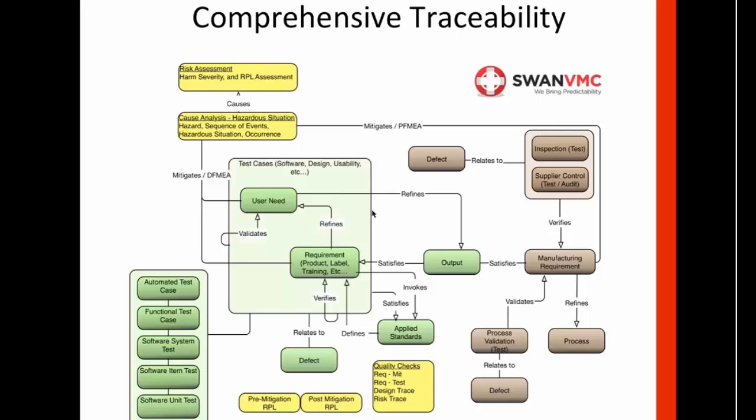So that's kind of the manufacturing piece of the flow chart. And of course, now when you overlay the yellow part, which is the risk management, essentially what we have are two work item types, and we're going to talk about those here in a second in detail. But the hazardous situation work item is a container for the hazard, and of course the way we come up and ferret out those hazardous situations is through risk analysis.